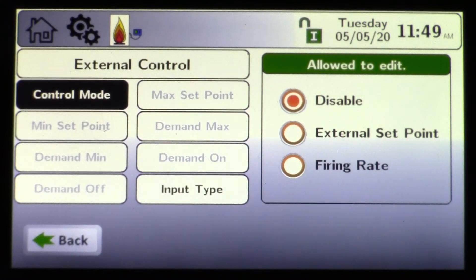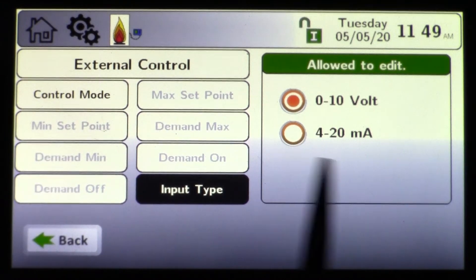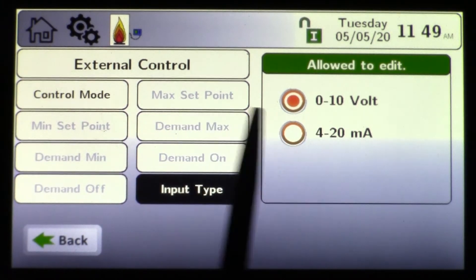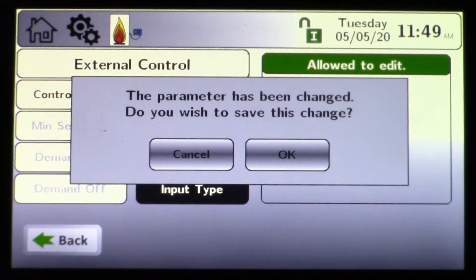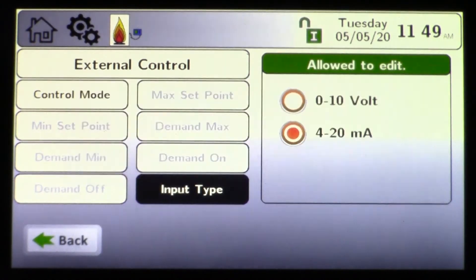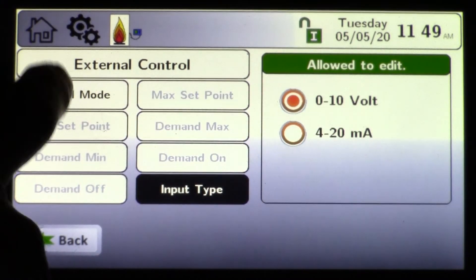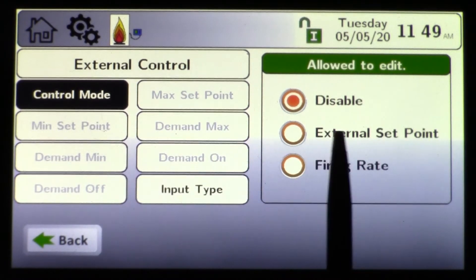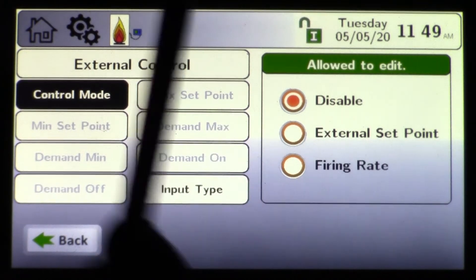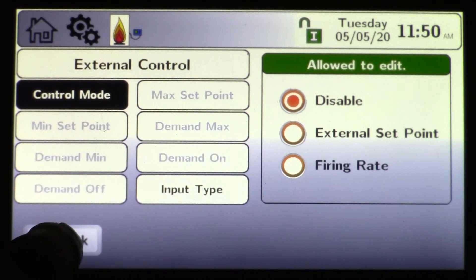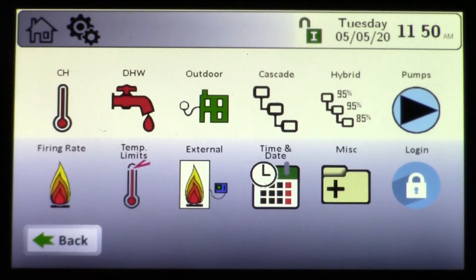Next we'll see the navigation of the program. Under external controls, this is where energy management can come in to control modulation or staging of a boiler. You have an input type — choose whether the system is using zero to ten volt DC or 4-20 milliamp. In this example I chose 4-20. You can go back to zero to ten, and under control mode we can use external set points or firing rate, depending on how the energy management company wants to operate that boiler.